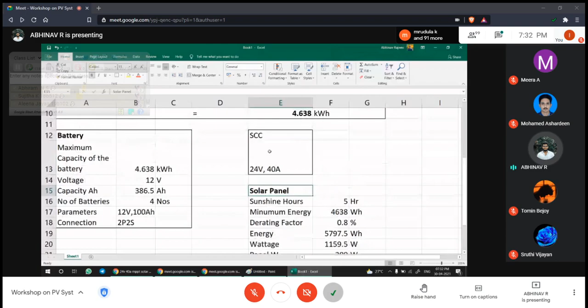So what would be the voltage configuration? It should be 24 volt, such that the MPPT can take it in. These are designed to take in anywhere between 12 to 24 volt on the output side, and on the input side you can use up to 70 volt. So you can go for 4 in series. For the time being, we'll be going for a 24 volt system. So this is regarding the solar panel. Now you get all the parameters, right?